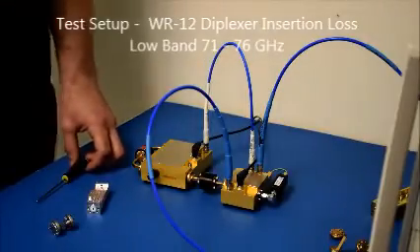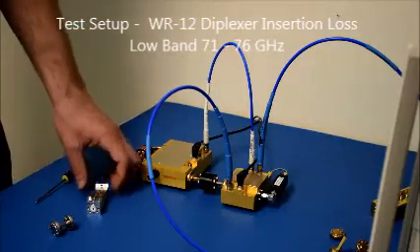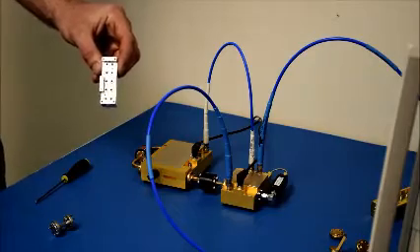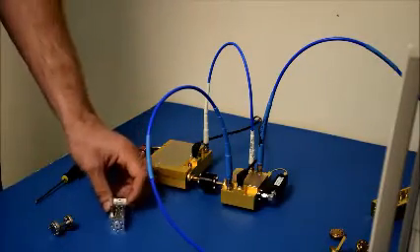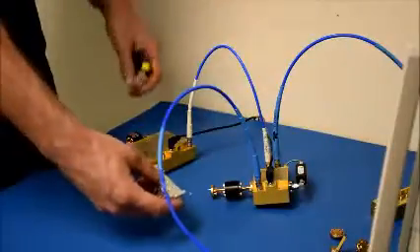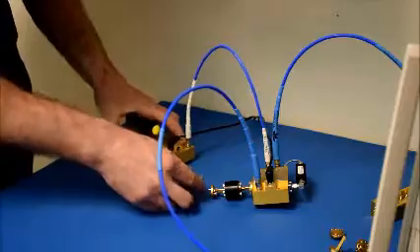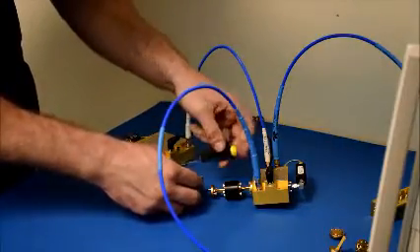Now that we have the system calibrated, we're going to demonstrate measuring the insertion loss of this WR12 diplexer, which has a low band of 71 to 76 GHz and a high band of 81 to 86 GHz. We've added a 1 inch piece of waveguide to the diplexer just to make the setup assembly easier. We'll be measuring the insertion loss of the input port to the low frequency channel.